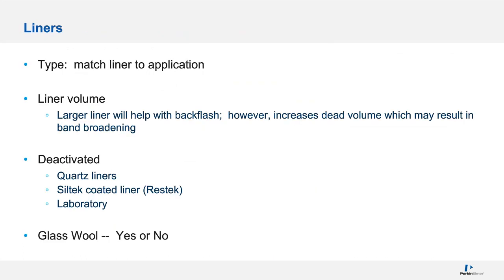Okay, now I'd like to move on to liners. The type that people have their favorite. I have my favorite. So it's whatever works for you, but there are suggestions from vendors on what liner is best for certain applications. For instance, purge and trap or headspace, you want to use the narrowest liner possible because the volume of the liner, even though it helps with preventing backflash, it also increases dead volume, which results in band broadening. Band broadening is bad because then you don't have as much signal to noise, you don't have as much resolution.